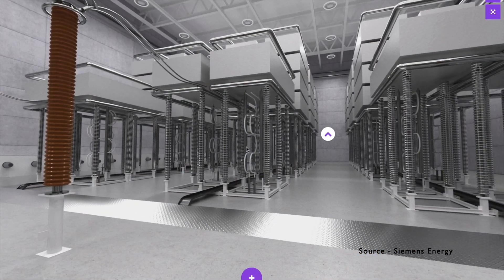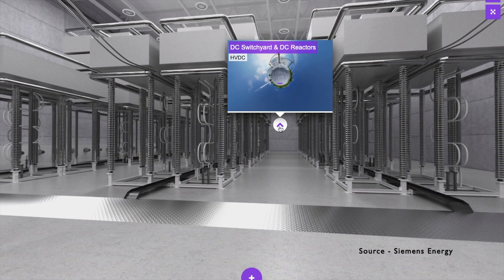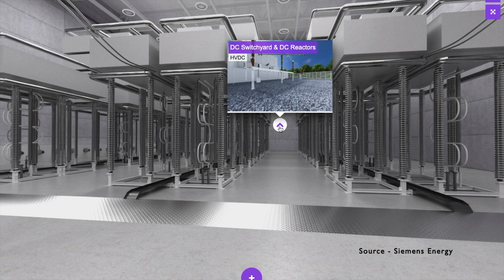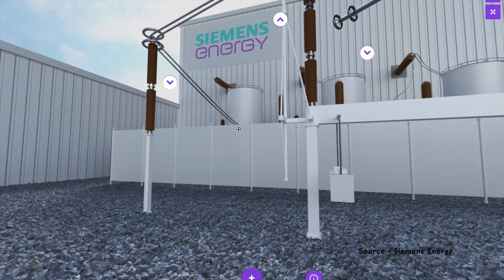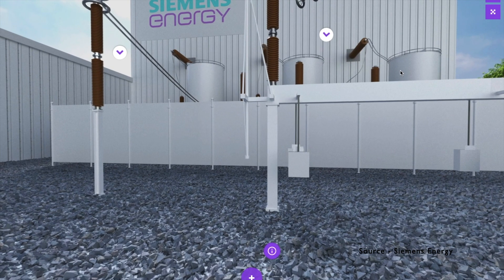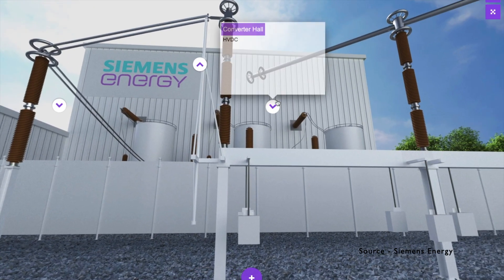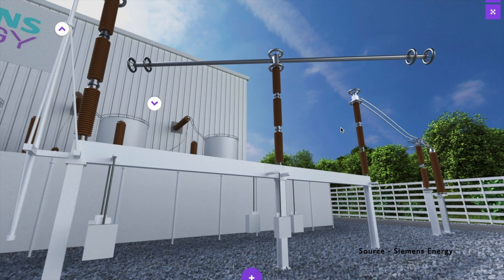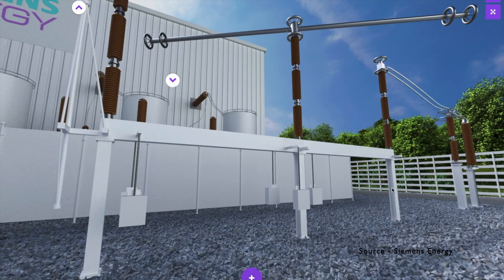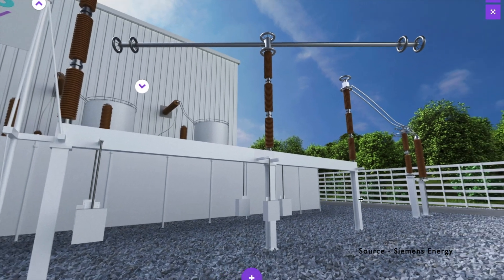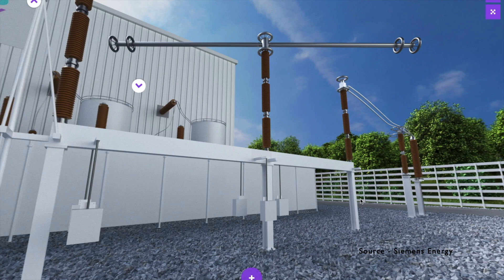This is the converter hall — it must be installed inside a building and cannot be installed in an outdoor application. Then lastly, we have the DC switchyard. You can see we have reactors here — this circular shape represents the reactor, which helps in smoothing down the DC output, reducing ripple in the DC supply, limiting DC fault current, and also reducing DC harmonics. You can also see the switches used here, which form the DC switchyard. As mentioned, we can have air-insulated or gas switchgear for DC. In this 3D model, AIS switchgears are used.